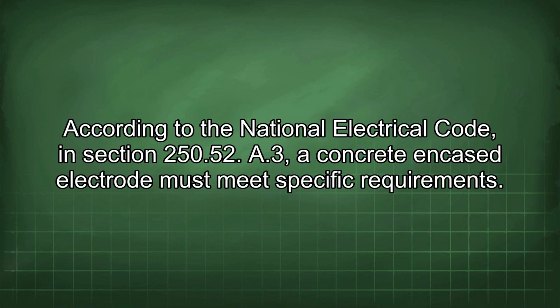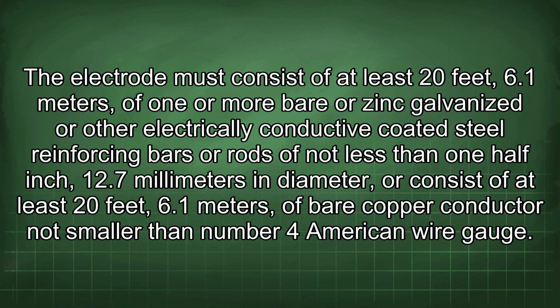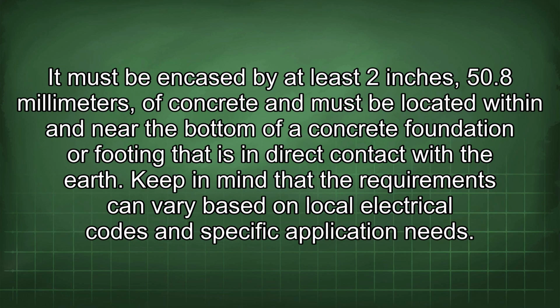According to the National Electrical Code, in section 250.52, a concrete encased electrode must meet specific requirements. The electrode must consist of at least 20 feet (6.1 meters) of one or more bare, galvanized, or other electrically conductive coated steel reinforcing bars or rods of not less than 1/2 inch (12.7 millimeters) in diameter, or consist of at least 20 feet (6.1 meters) of bare copper conductor not smaller than number 4 American wire gauge. It must be encased by at least 2 inches (50.8 millimeters) of concrete and must be located within and near the bottom of a concrete foundation or footing that is in direct contact with the earth. Keep in mind that the requirements can vary based on local electrical codes and specific application needs.